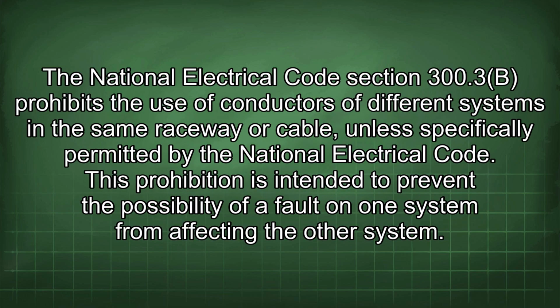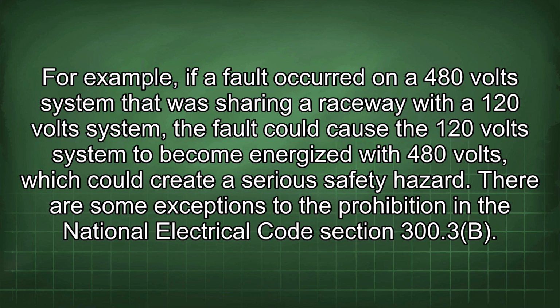The National Electrical Code section 300.3(B) prohibits the use of conductors of different systems in the same raceway or cable, unless specifically permitted by the National Electrical Code. This prohibition is intended to prevent the possibility of a fault on one system from affecting the other system. For example, if a fault occurred on a 480-volt system that was sharing a raceway with a 120-volt system, the fault could cause the 120-volt system to become energized with 480 volts, which could create a serious safety hazard.